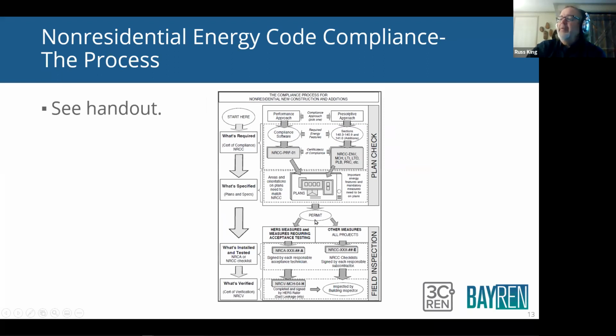So the permit happens, okay? Then the measures, the features that go into the house, or the building, get broken into two basic categories. There's stuff that has to be inspected by either a third-party inspector or the installer. There's special tests that have to be done, like duct leakage testing, airflow testing. And then there's other stuff that are just verified by the building department. So we're going to break those into two different categories.